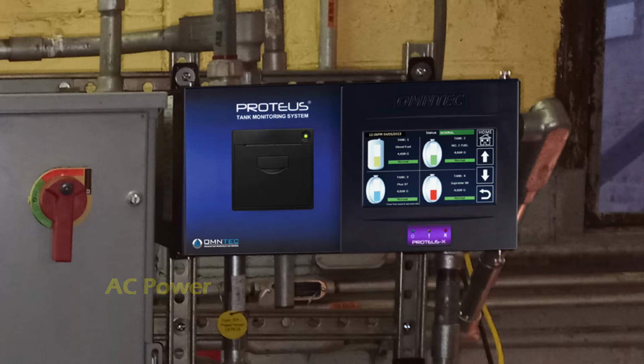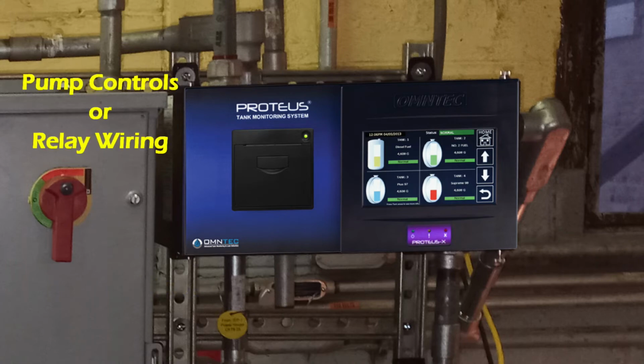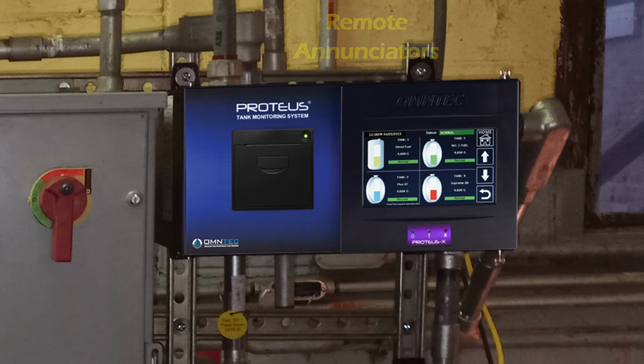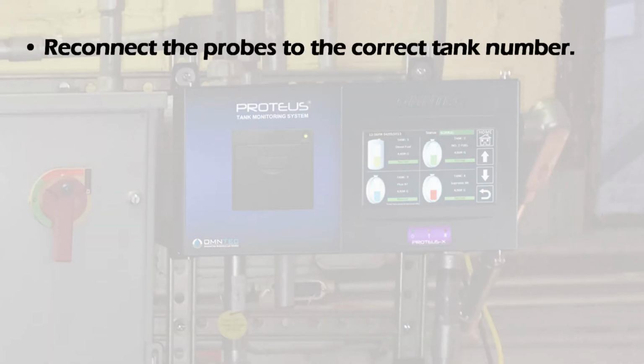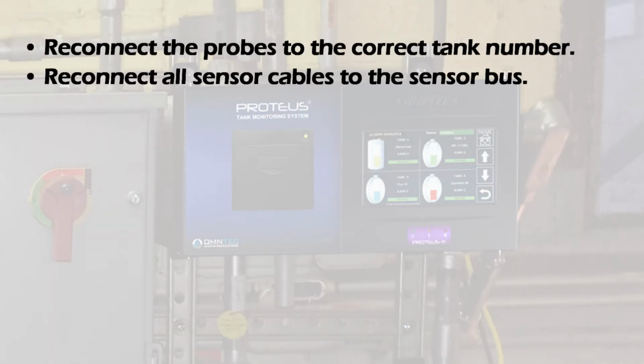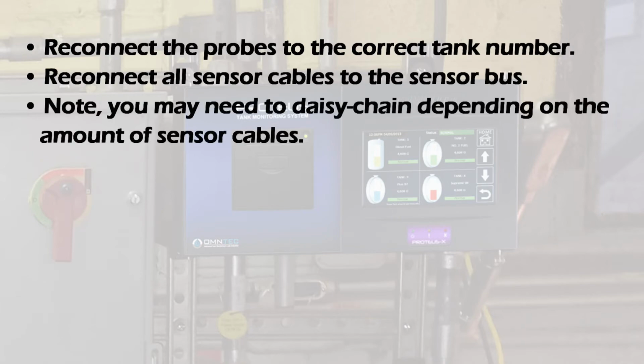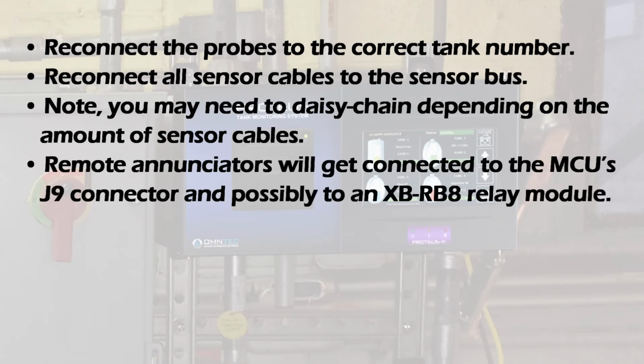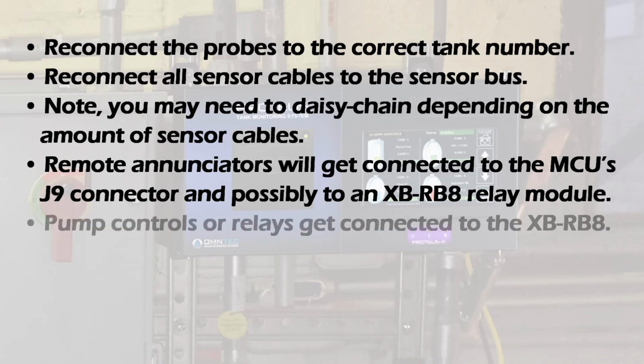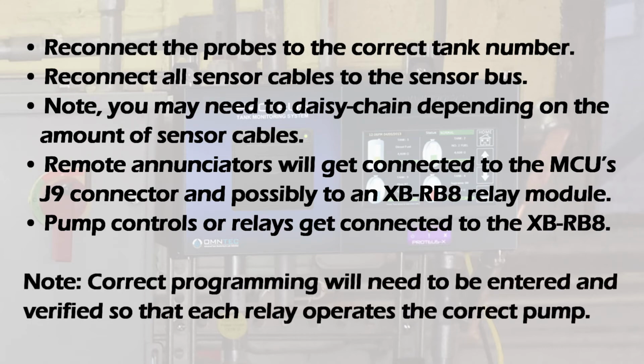Reroute the AC power, probes, sensors, pump controller relay wiring, and remote annunciator cables to the appropriate knockouts for the model controller being installed. Reconnect the probes to the correct tank number. Reconnect all sensor cables to the sensor bus. Please note, you may need to daisy chain depending on the number of sensors. Remote annunciators will get connected to the MCU's J9 connector and possibly to an XB-RB8 relay module. Pump controller relays get connected to the XB-RB8. Also note, correct programming will need to be entered and verified so that each relay operates the correct pump.